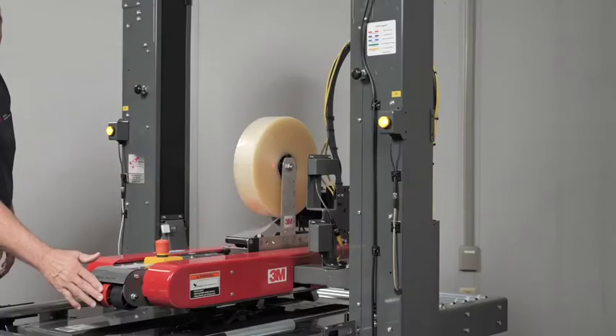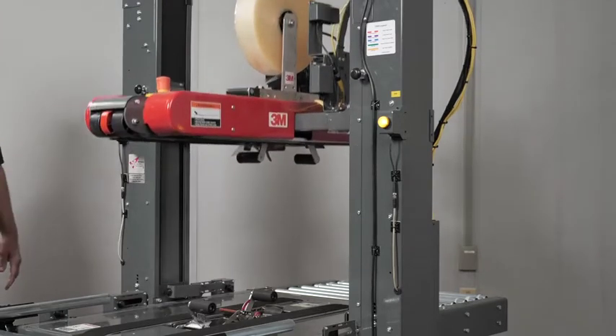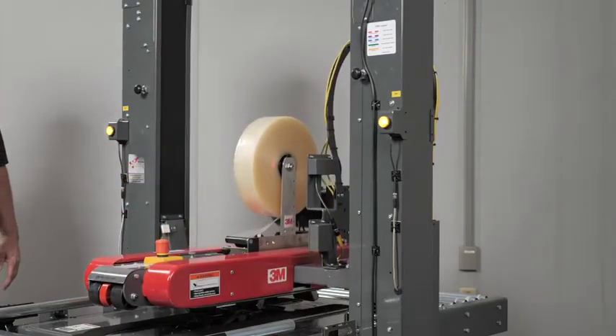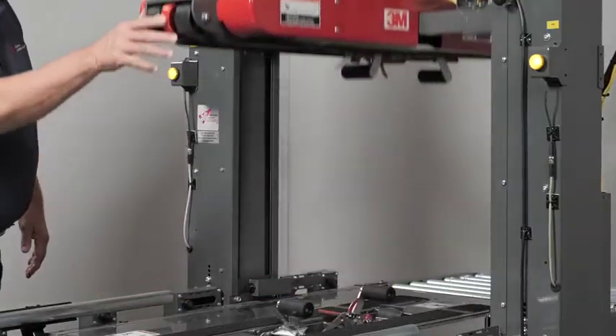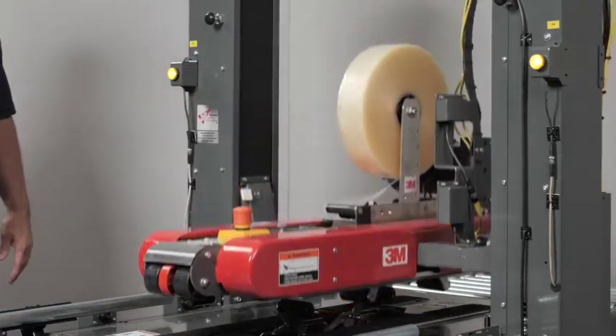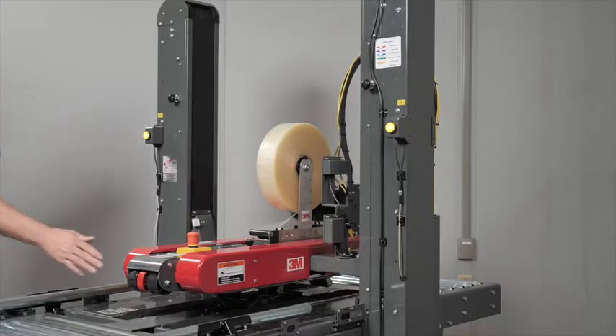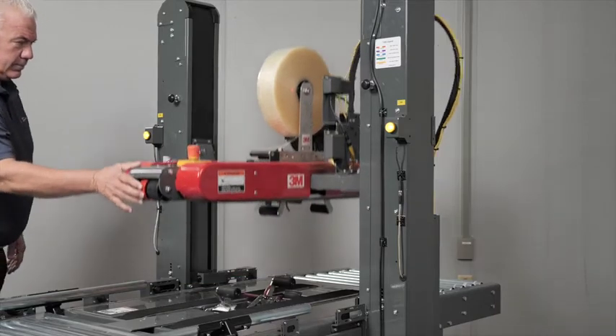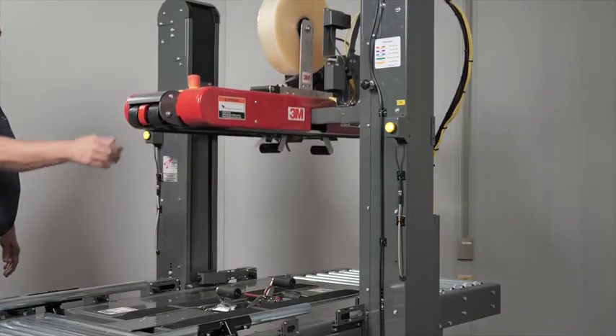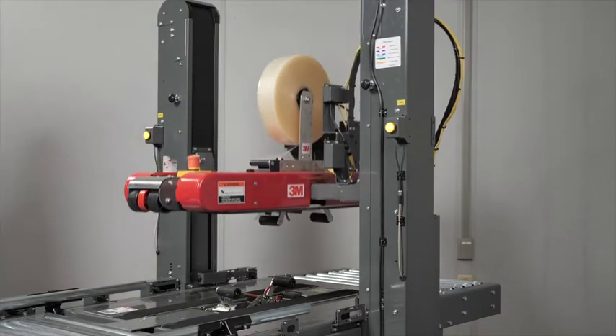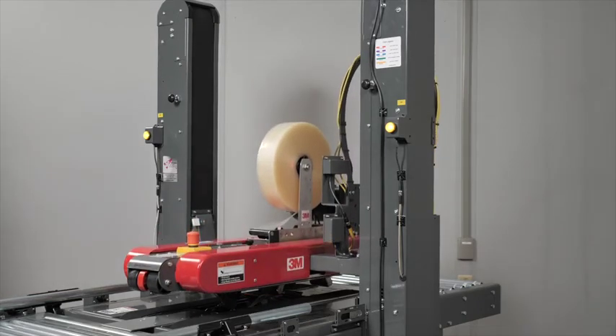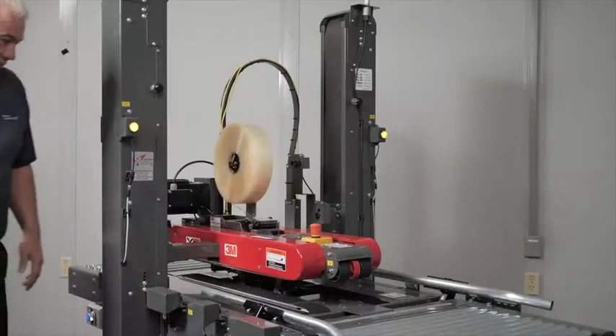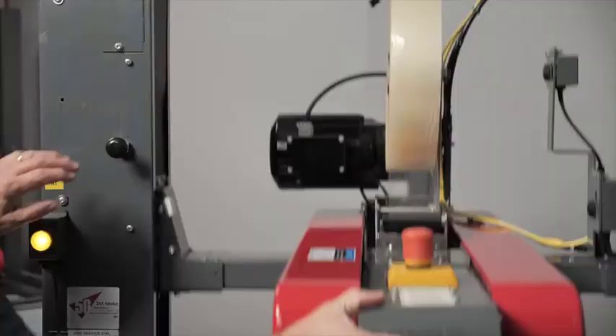The upper assembly raises by depressing the red actuator switch. The movement is detected by a proximity sensor under the cover. The PLC controller senses the on condition of the proximity sensor and energizes the solenoid valve that provides air pressure to the air column cylinders, raising the upper assembly. Check to ensure the upper assembly raises and lowers smoothly, and note the red actuator will wear over time and will need to be replaced for proper operation.